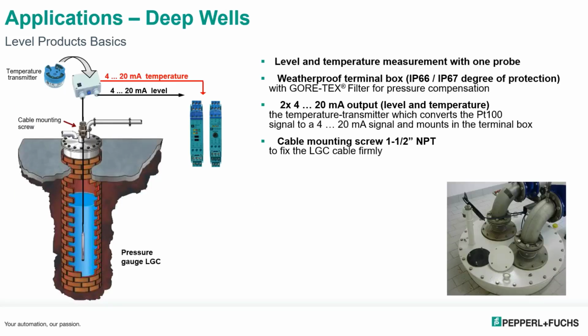This shows you an application of the LGC, and you see it going down the probe. We actually offer process connections with a housing that can house the temperature transmitter. So this LGC probe can also give you temperature outputs. With a temperature transducer, you can get a 4 to 20 milliamp output for the temperature inside there, as well as a 4 to 20 milliamp output on the level.